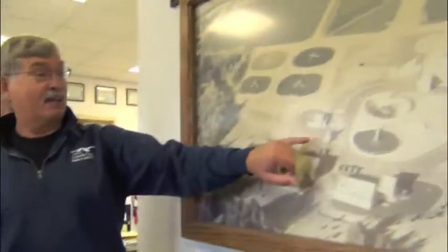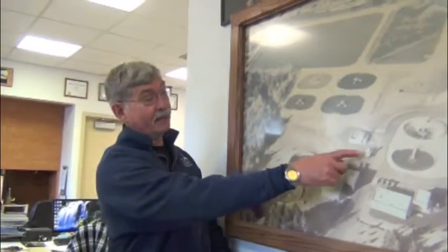We have a new picture up. Wastewater is basically the same, though. You take raw sewage, we put it into a basin. I can show you on this picture. This is the simplistic version. It comes in here, we screen it, take all the rags and garbage out, the fish, the garbage, the toys, everything out. We send it to the next unit. That unit takes all the inorganics, the heavy solids. Sand gets in the line, gravel can get in line when there's breaks.